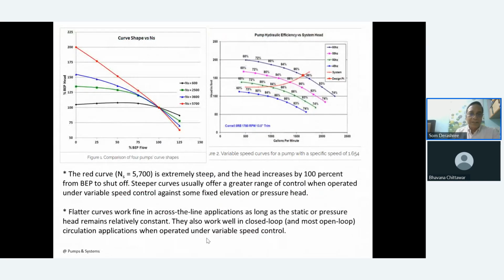There's another curve, specific speed, most often not a very popular dimension or entity to look into, because operating and maintenance staff already have an entity in their place. But I'm talking of how to select at the design stage. That's where you have to have this parameter, which is very important. Now here it is giving you specific speeds. So red is the highest, that is the axial flow, and 5,700 Ns.